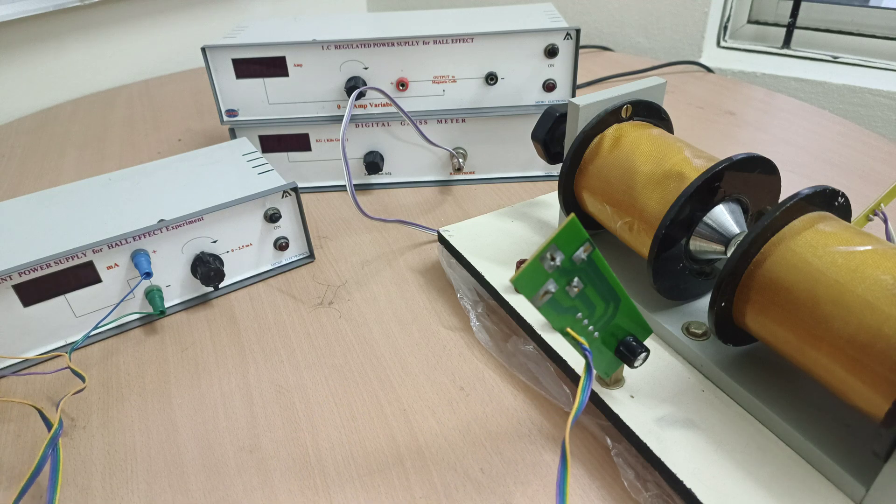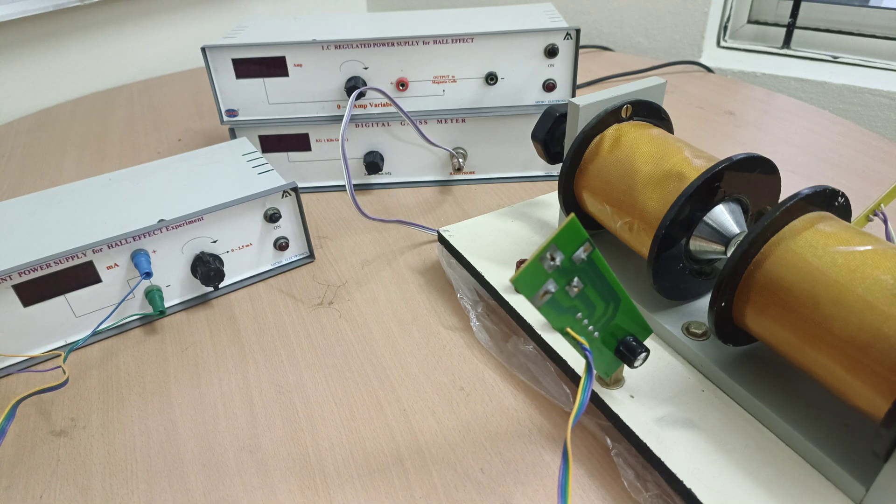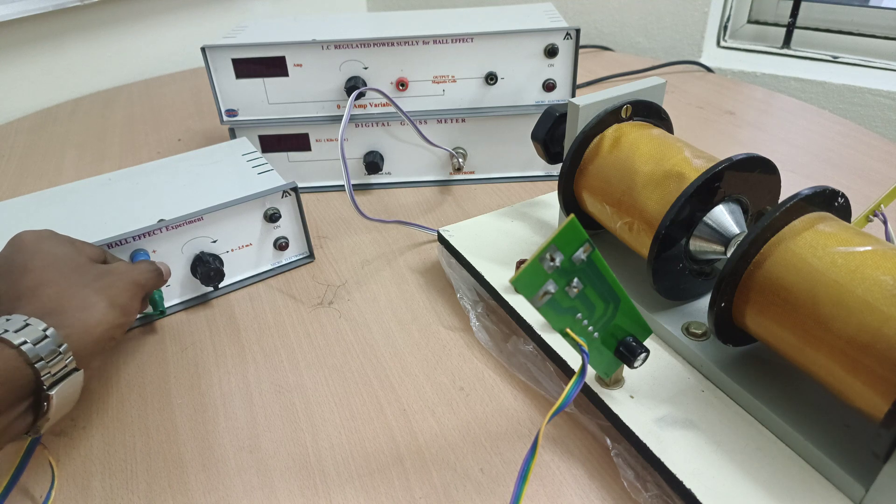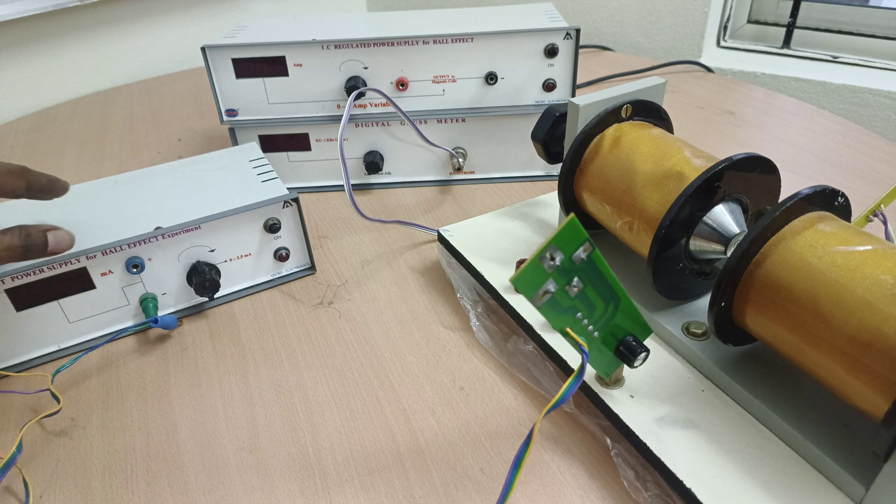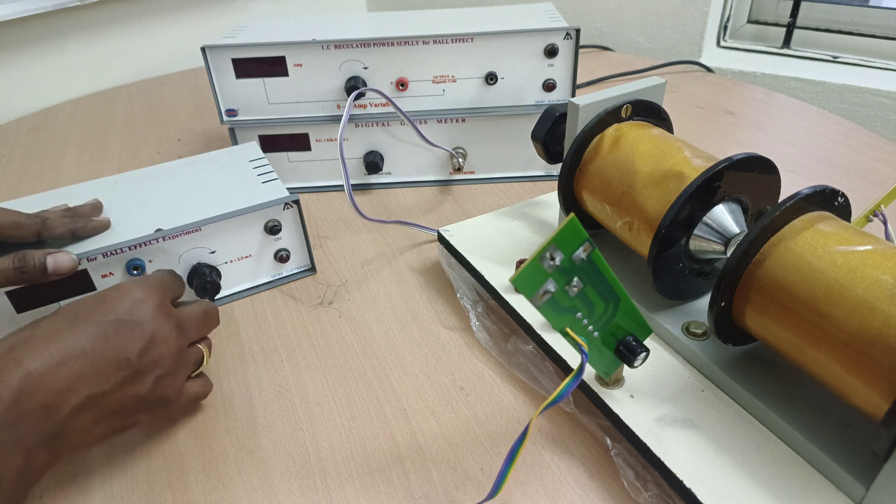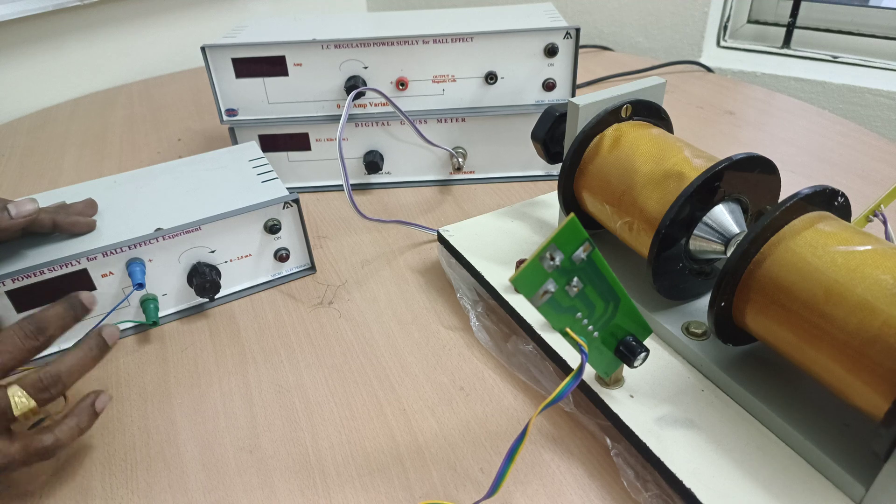Gauss probe is connected to the gauss meter and Hall probe is connected to the constant current power supply. Here you can see blue one is connected to blue terminal, very simple connection, and the red one is connected to red.